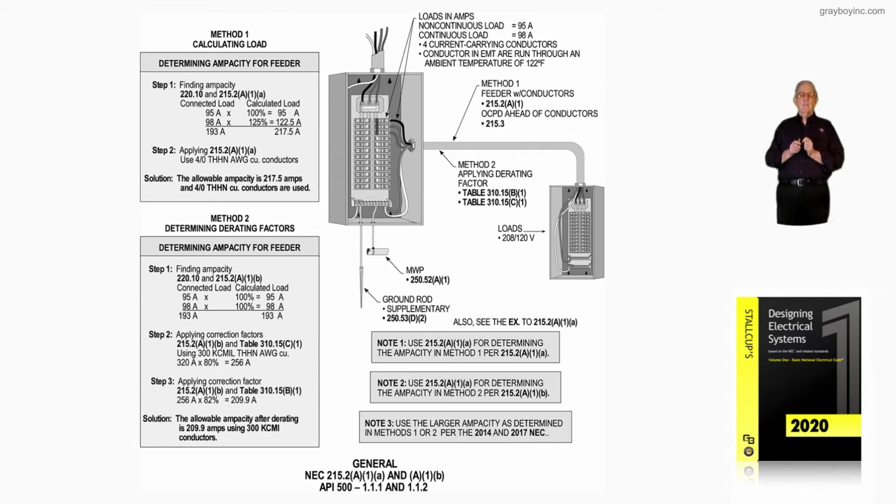And we have a question. What is the allowable ampacity of 16 number 12 AWG THHN copper conductors with diversity located in the same raceway? Now notice you're only going to load these conductors, half of them. Now table 310.16 says, all right, number 12 conductors in the 90-degree column is 30 amps.